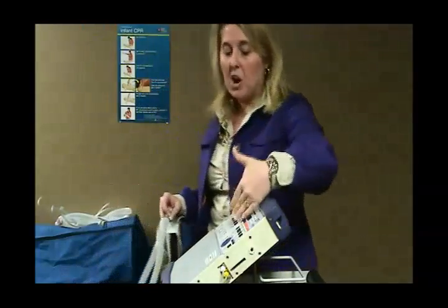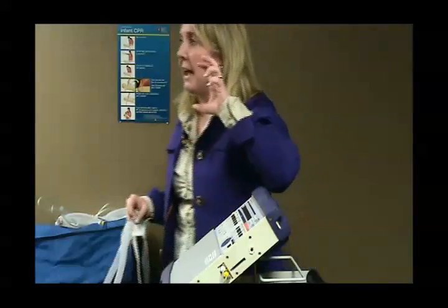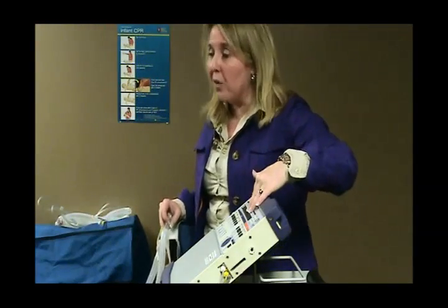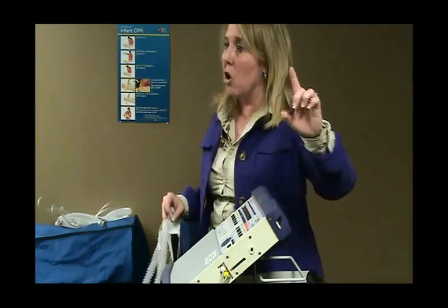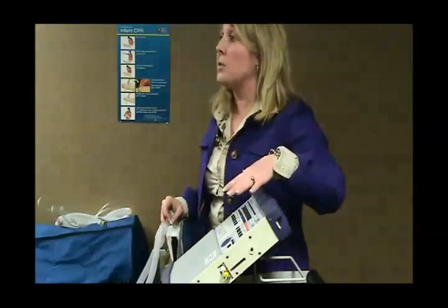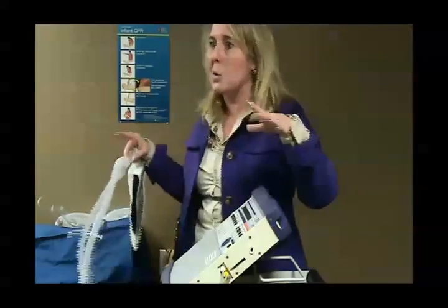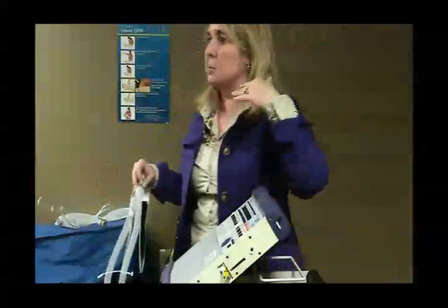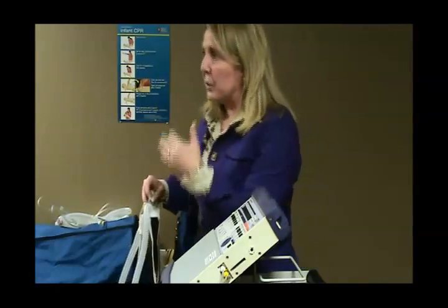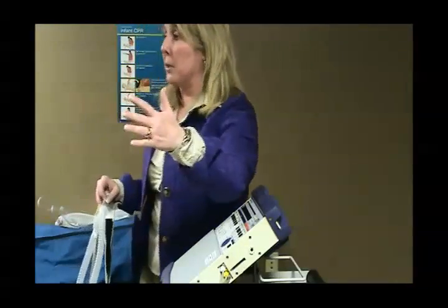So the ventilator is designed to alarm every time they hit high pressure. But it also has a feature in the back menus called HP delay. It allows you to set it up so that the patient can cough twice consecutively. You will get a flash on the screen, high pressure, but you won't get an audible alarm. So if you ever see a flash on the screen, high pressure, but it doesn't sound, there's nothing wrong with the ventilator. It's set up for a high pressure delay. That's to allow you and the patient some peace and quiet when they cough and can clear their own secretions. Please know that it is still going to pop off at the high pressure, so their lungs aren't going to see too much pressure, and if it occurs more than twice, the ventilator will start audibly alarming as well. So it's a really nice feature.